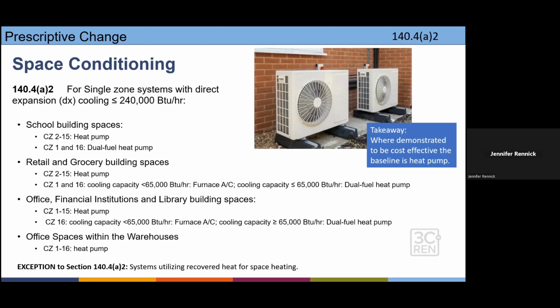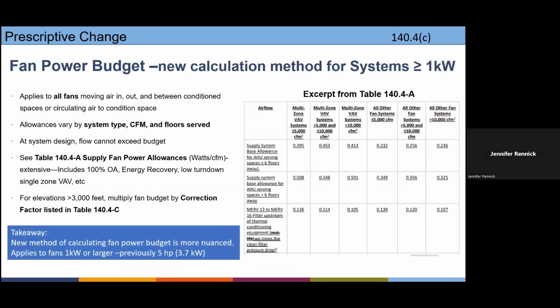You'll get a copy of the slide. But for example, if you're going to be working on a school building now in climate zones 4, 5, 6, 7, which is part of our tri-county area, the baseline is a heat pump. Along with that are new calculation methods for the fan power budget. This is just an excerpt of the table, and it continues on quite a bit in the manual.